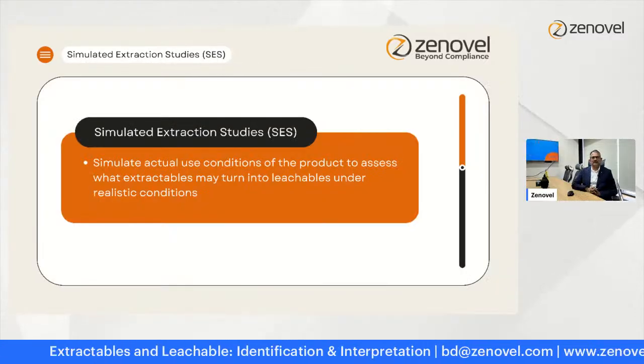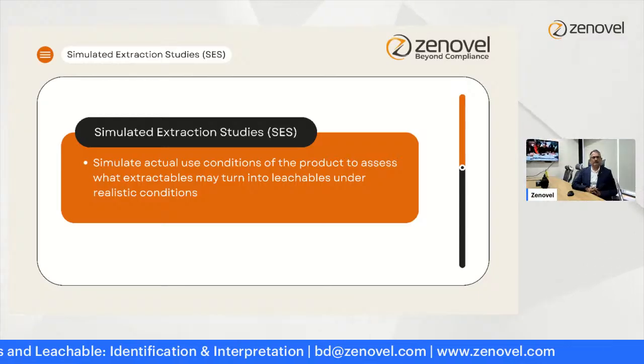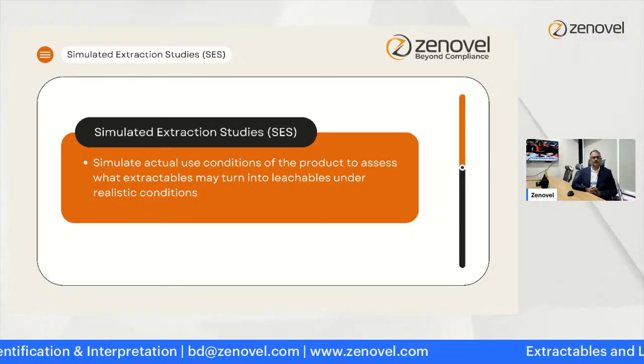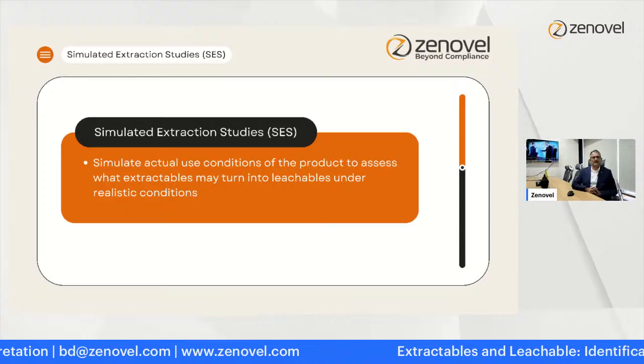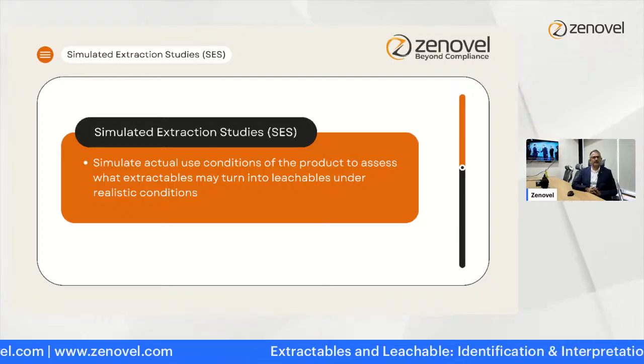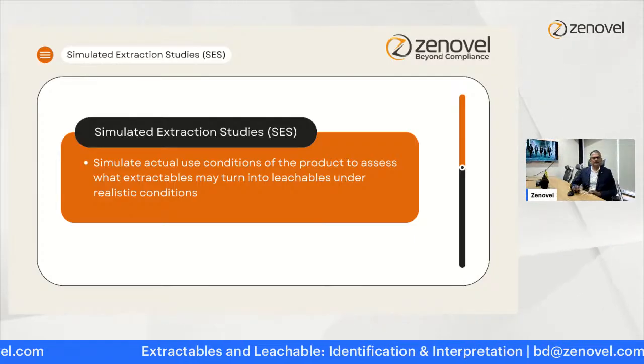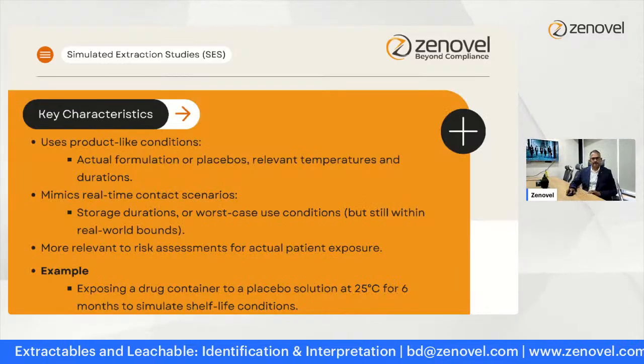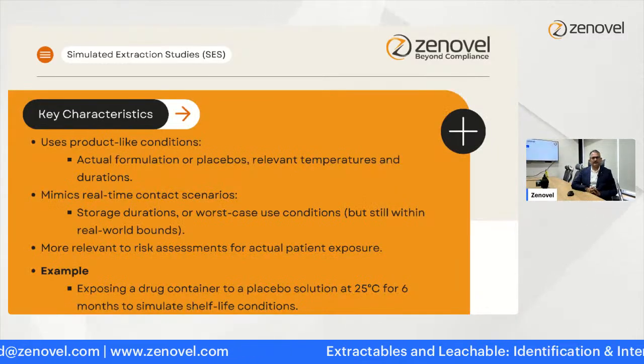The simulated extraction studies generally simulate the actual use condition of the product to assess what extractables may turn into leachables under realistic conditions. Key characteristics of the simulated extraction studies.